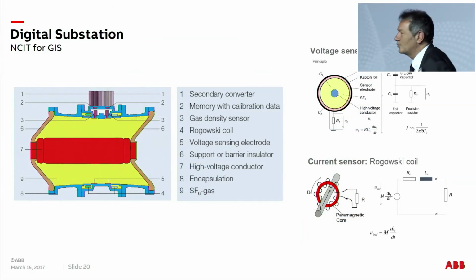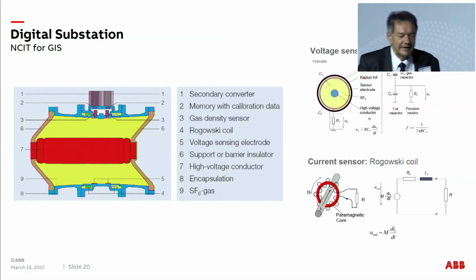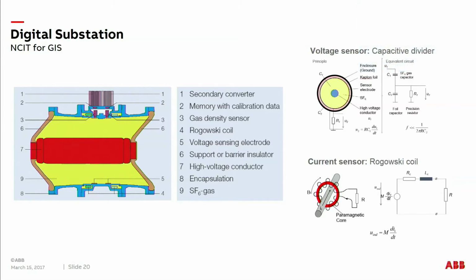In the case of a gas-insulated switchgear, for those who really want to know how it works there, you remember this gas-insulated switchgear I was showing? This is now just such a sensor. Here in the sensor, the middle part is the conductor, high voltage. Here you have ground potential. In between you have an insulation gas. So high voltage, high current, ground potential, you can touch it. And in the case of GIS, we put electronics directly at the sensor, and then you have two Rogowski coils and two capacitive rings sensing the current and the voltage.